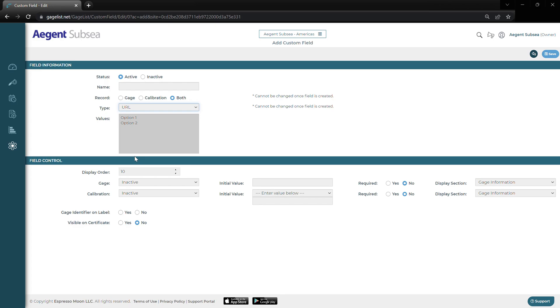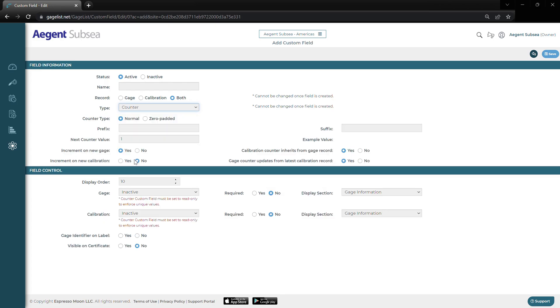We also have a URL field that will allow us to paste hyperlinks on our gauge or calibration records. And then last but not least, we have our counter field. This is going to be an auto-increment field that allows us to auto-increment based on a new gauge record or a new calibration record. We could also add a prefix or a suffix to it, so that way if we have multiple locations, we can know which site it's coming from if we export the records.